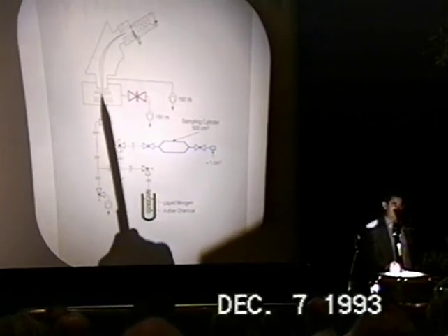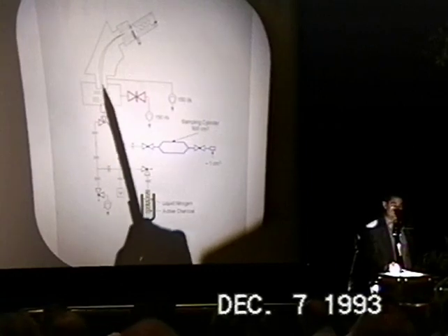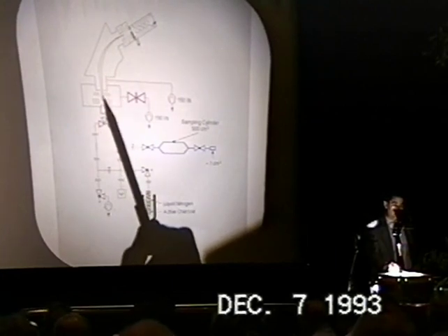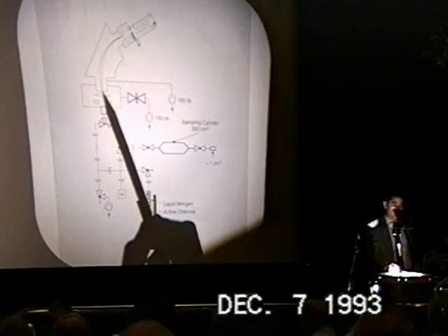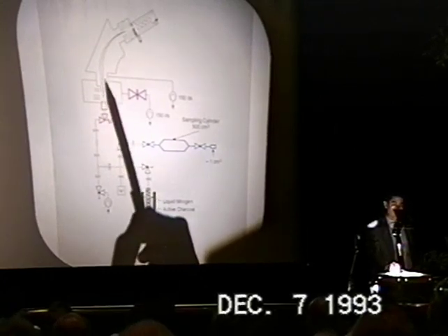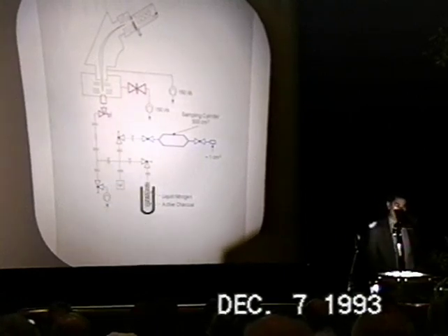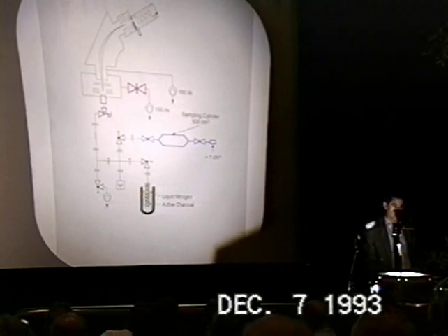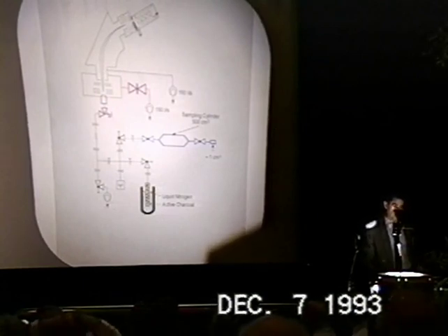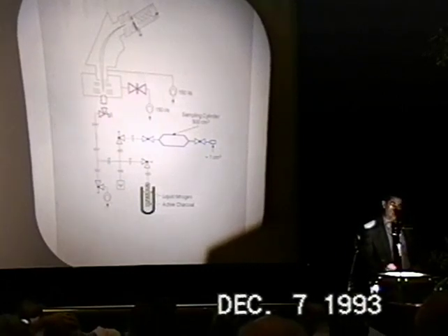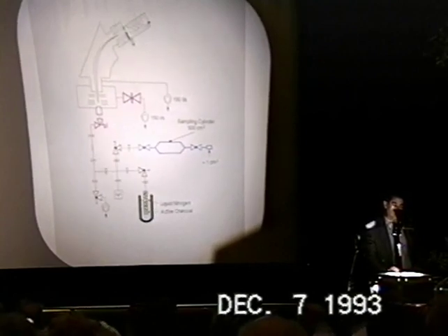It's a kinetics, I would say, controlled by the impedance through which the gas is pumped through the interconnection between these two sections by the pump, which is still working for the analyzer section. So we are not in a dynamic way of handling the situation, and not in a really static way either. By this means we have quite a good increase in sensitivity, and on the other hand, we do not have really any memory problems.